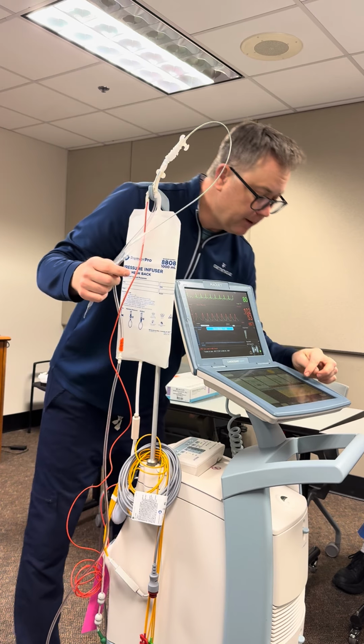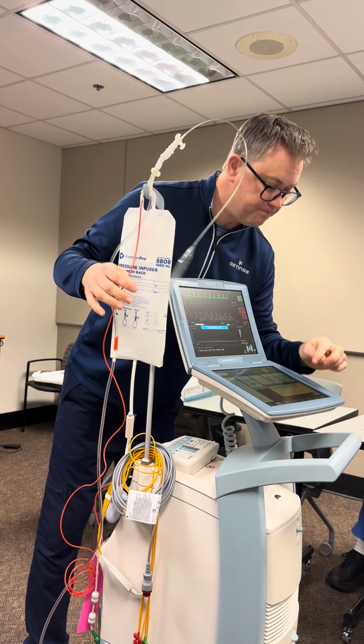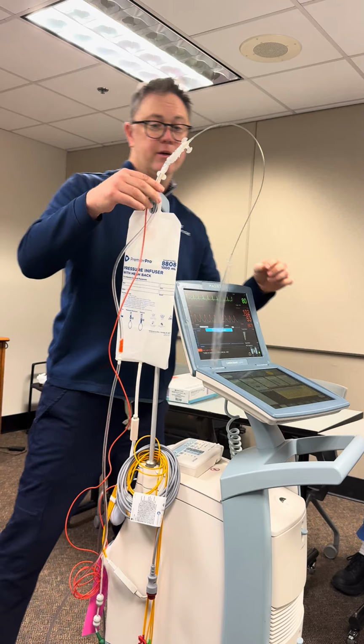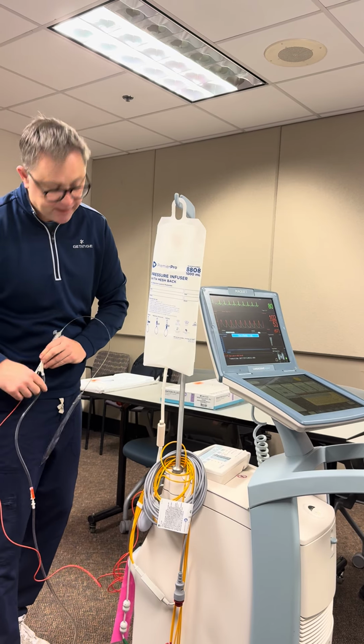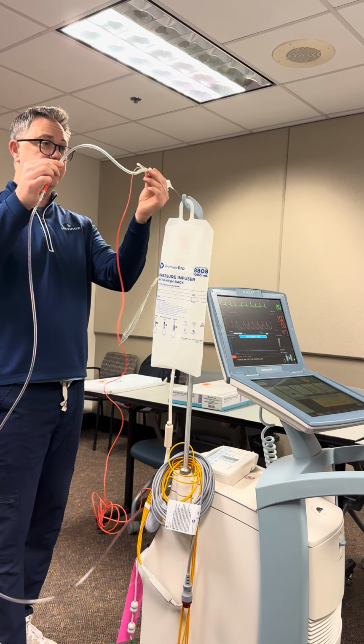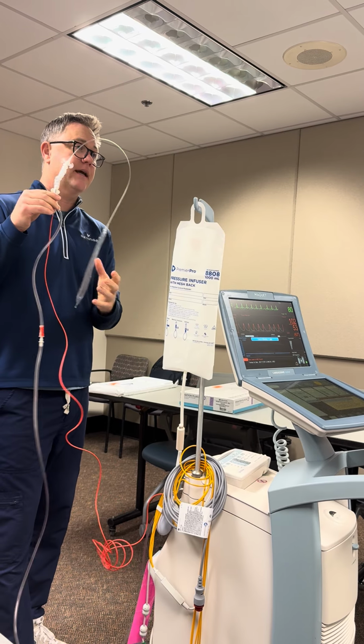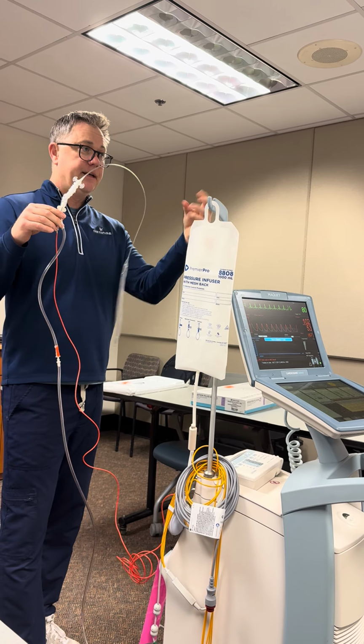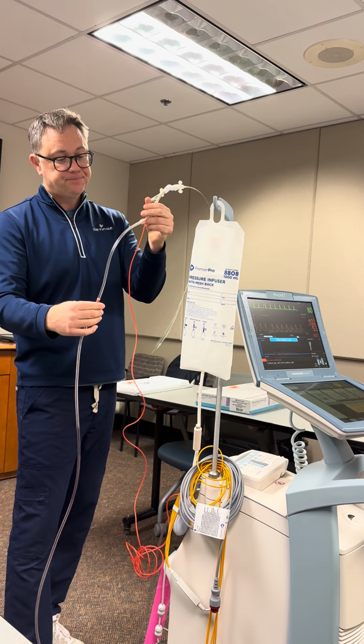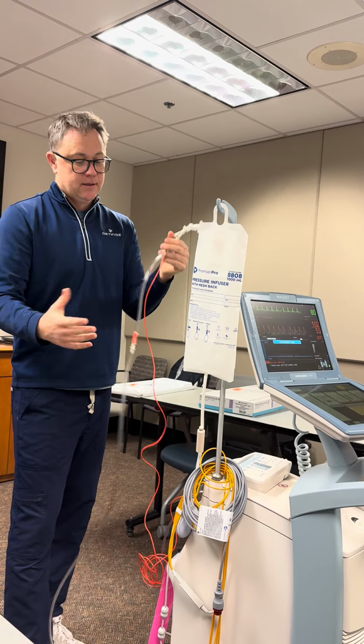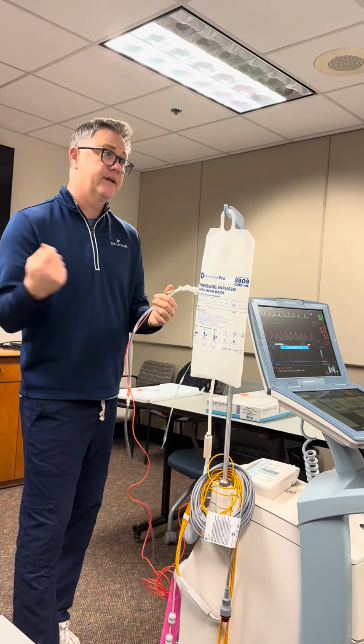So if I come in here, go to my help screen, the first thing it's going to tell me to do is check my helium line for blood back. If I see any blood in here, that's an indication that my balloon catheter is ruptured. Inflating and deflating, we've sucked some blood back in, and the balloon catheter is going to need to be removed.